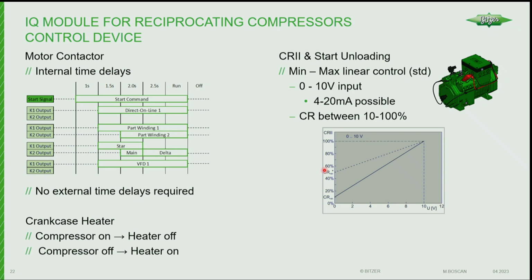All right. If you do change the minimum, by the way, like this one's 10%, that one's 50%, you do change that slope, so the granulation between 0 to 10 will change, but that's all. The CMRC does that in conjunction with your rack controller.